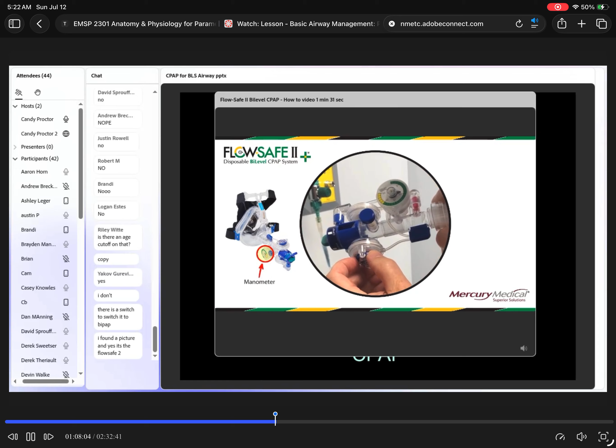Here are some reminders for successful therapy. The device is intended for patients that have respiratory distress and are not requiring respiratory failure protocols. Nebulizer treatments can only be given in the CPAP mode. Do not over-tighten the mask straps. Patients should have effective spontaneous ventilation. Healthy people can reduce the pressure to zero during inhalation, giving a false impression that the IPAP is lower than the EPAP.